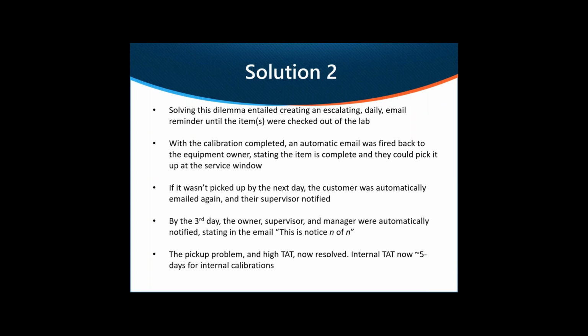So to fix this problem, I was able to use IndySoft and use an escalating daily email reminder. When the calibration was finished, an email was fired back to the equipment owner or the person that dropped it off and said, hey, your equipment is done, come pick it up out of the lab. If they didn't pick it up by the next day, then it went to them again, and now it went to them and their supervisor. If by the third day it wasn't picked up, it went to them, their supervisor, their manager, and then if there was a fourth day, it went to the director, and it would preface it on the third day, this is notice 3 of 3.